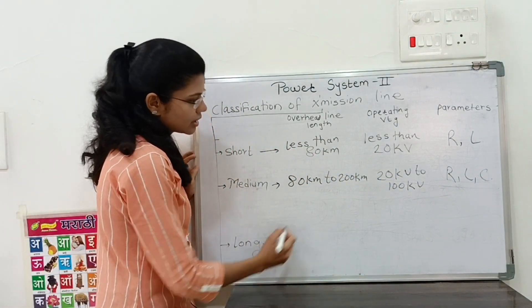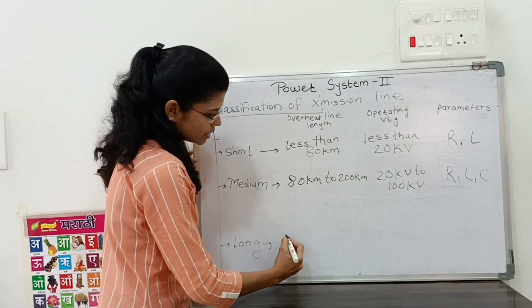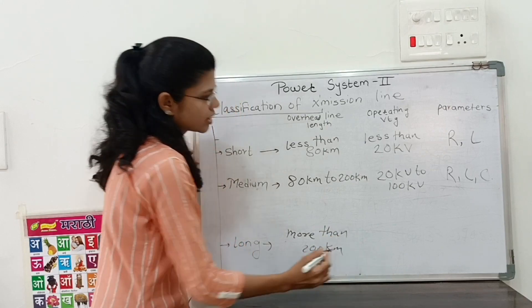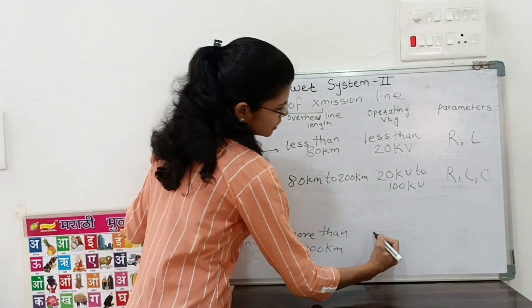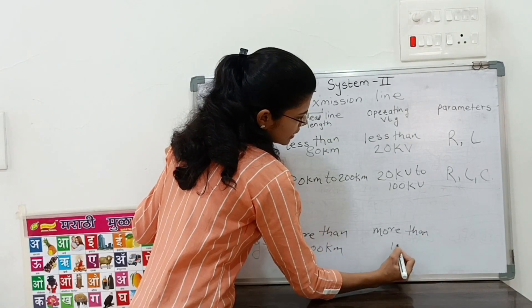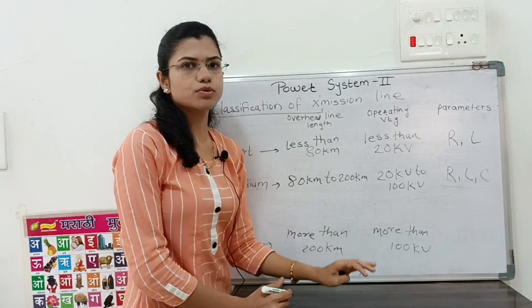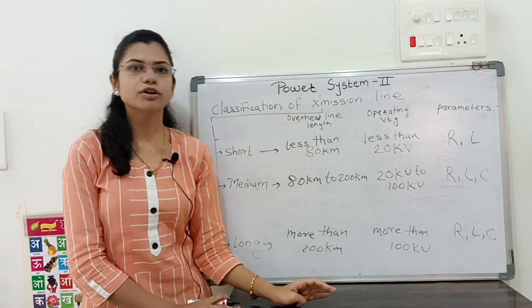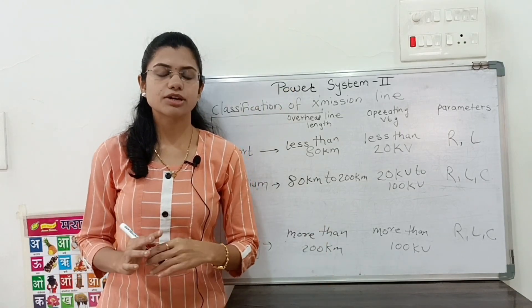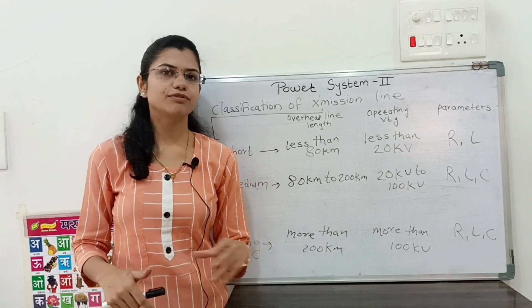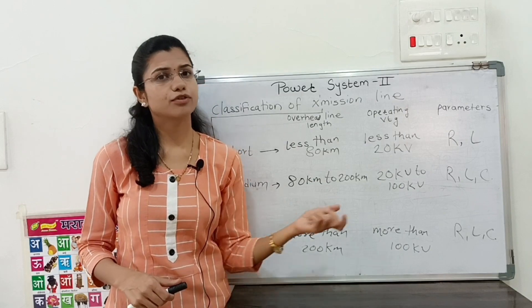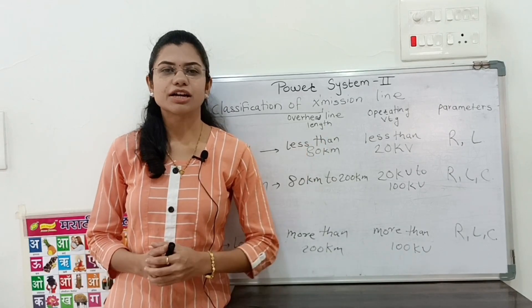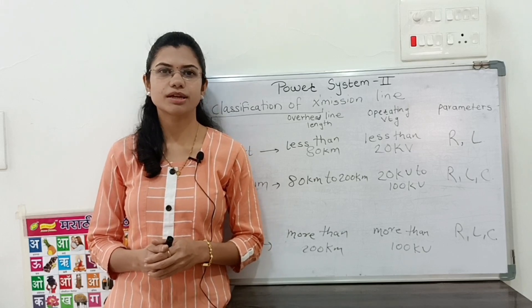For the long transmission line, the overhead line length is more than 200 km and the operating voltage is more than 100 kV. The parameters present are R, L, and C. G is neglected because the leakage current is very very small, and therefore the effect of shunt conductance G is negligible. However, in practical cases, G is present.